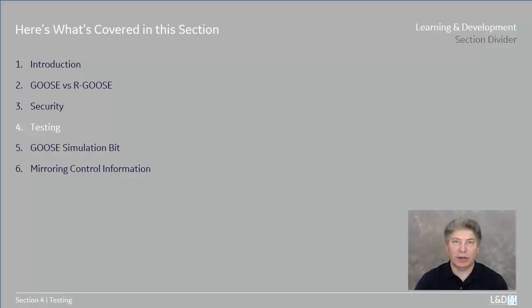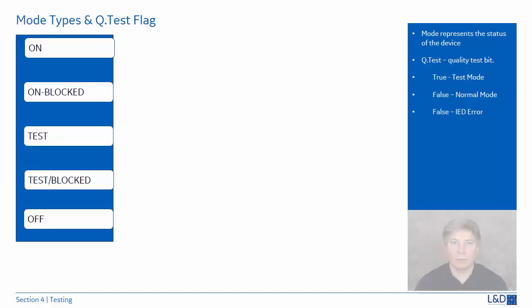In this section, we'll take a look at how testing is handled in IEC 61850. Let's discuss what the mode types and quality test flag represent. The mode represents the status of the device. The Q.test bit is the quality test bit. When the device is in test mode, the bit is set to true. For normal operation or non-test mode, it is set to false. The Q.test bit can only be true if the IED is in test mode and the IED is not experiencing an error. Let's review these different configurations.